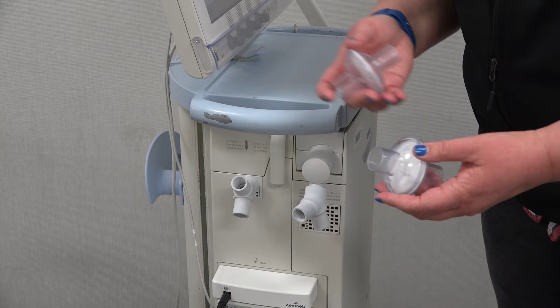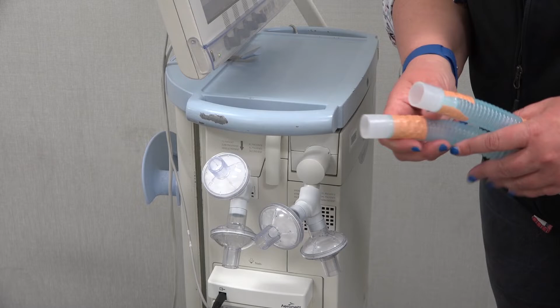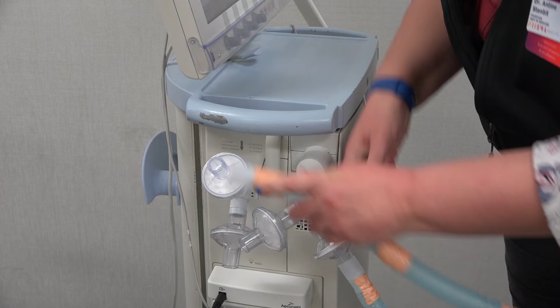You can use clear or white tubing for one patient and blue for the other, or whatever you have available in your hospital system. The next thing you want to do is take your filters, and here we have the universal bacterial and viral filter that you can attach. You can also use the HEPA light filter, which is what we would probably do in this situation instead of using the universal bacterial and viral filters, but these are what we have available right now. You want to make sure that they're seated well on the VESper device, on both the inspiratory and the expiratory limb. And then you place the tubing for your patient on each side.